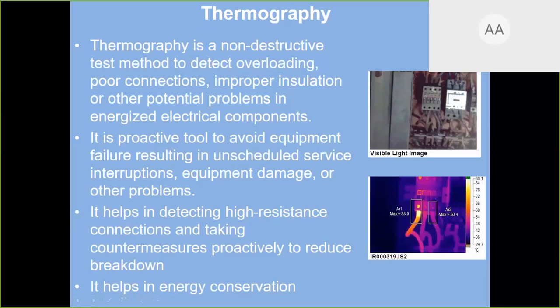Thermography will do this. In a panel where wires are there, if there is overloading in the wire, you cannot see it with the naked eye. There is a poor connection, improper insulation, you cannot see anything here. But with thermography, it will show a different color in the wire where there is overloading. So this thermography camera will definitely tell you by checking each distribution board, each panel.